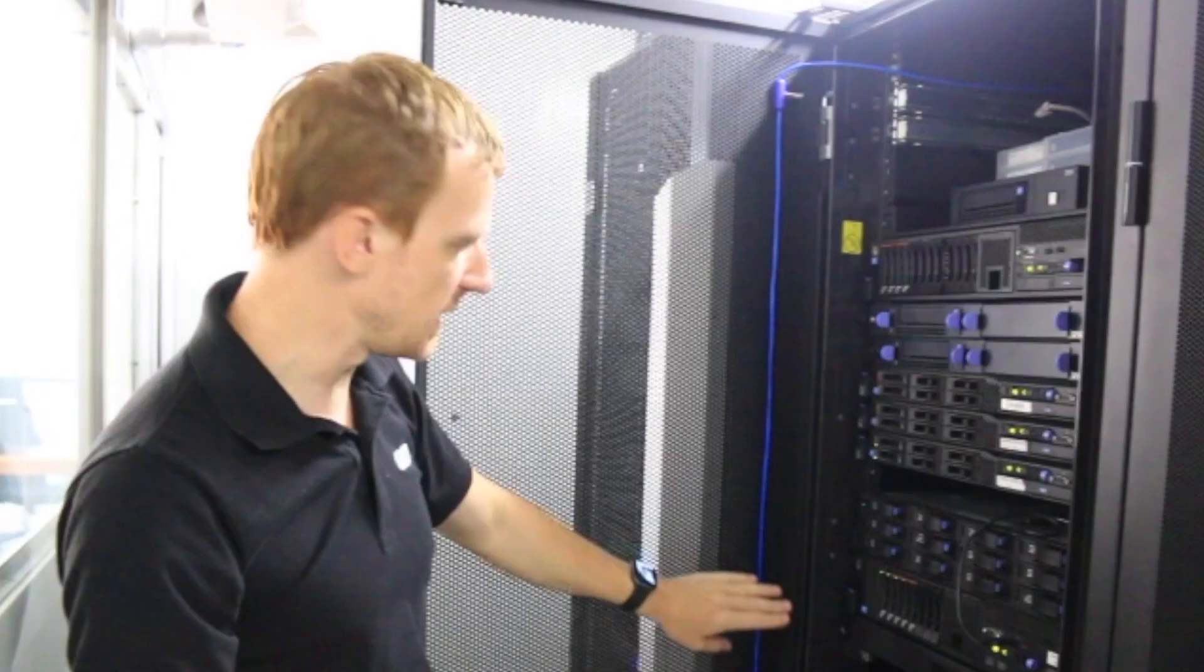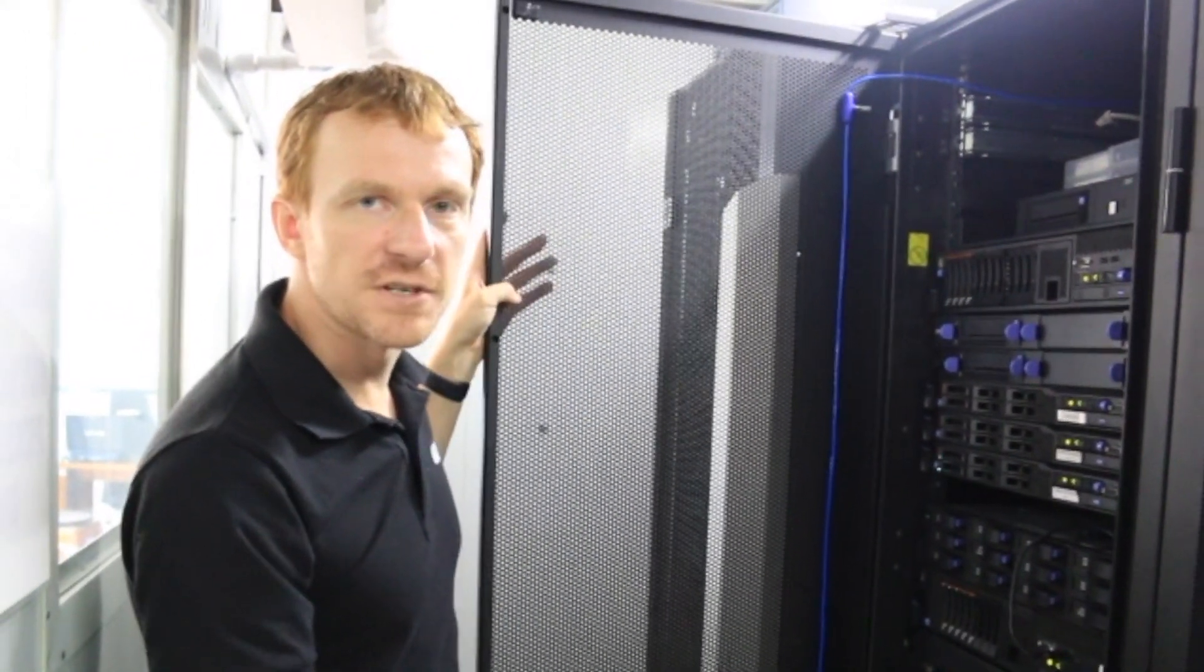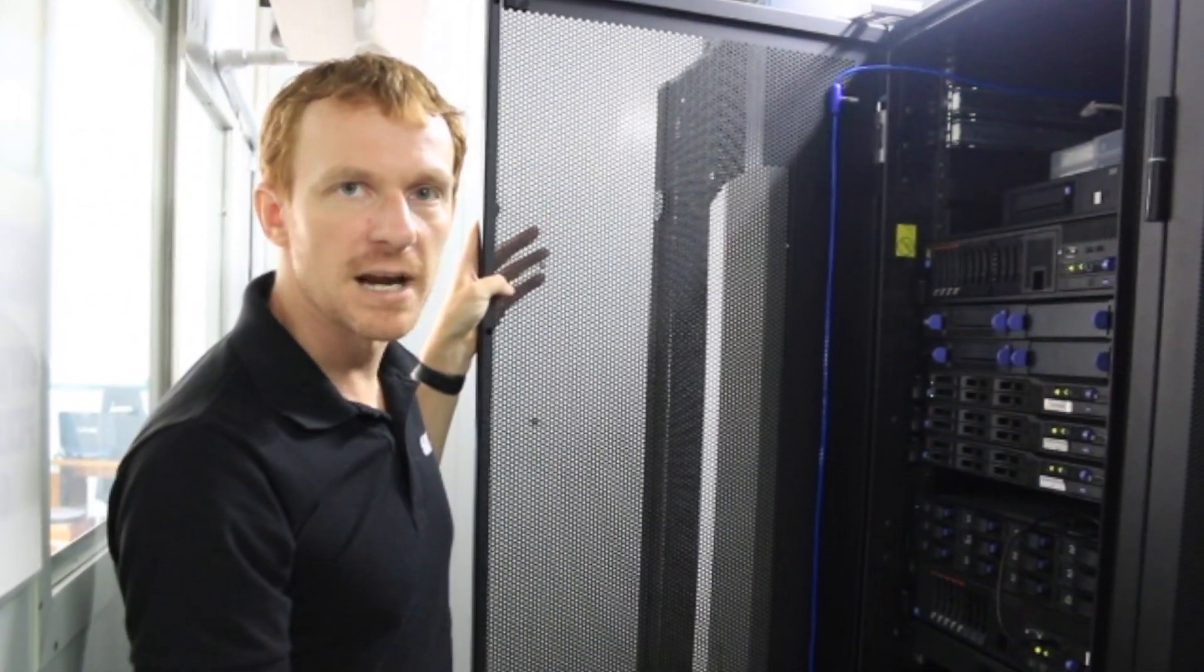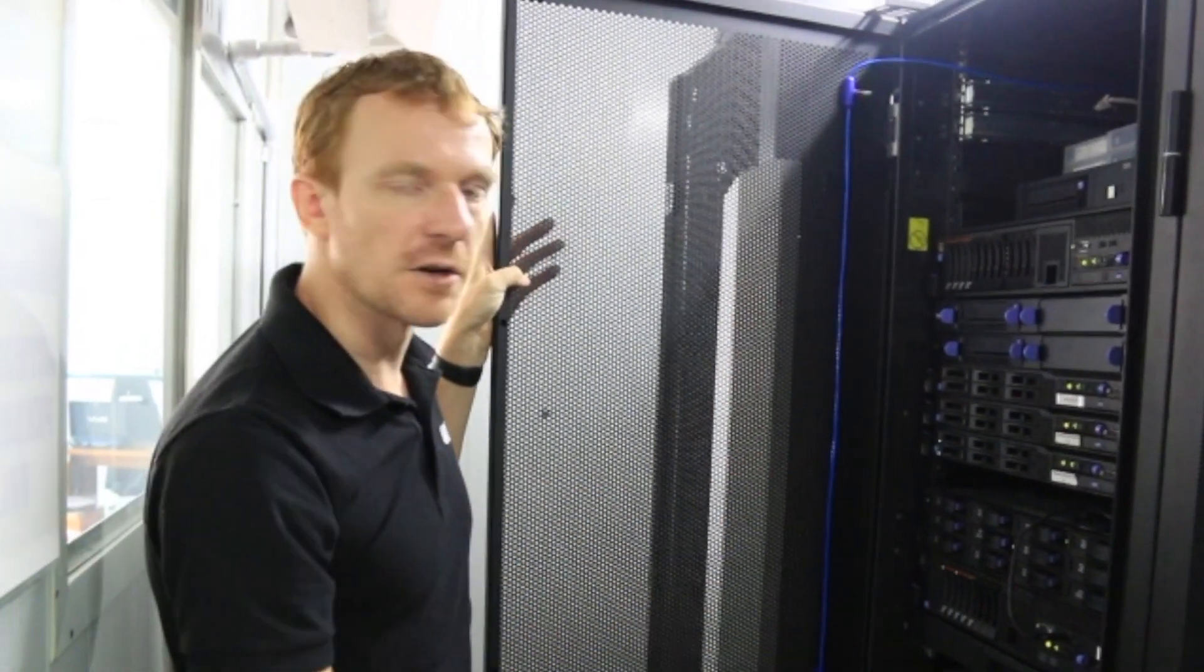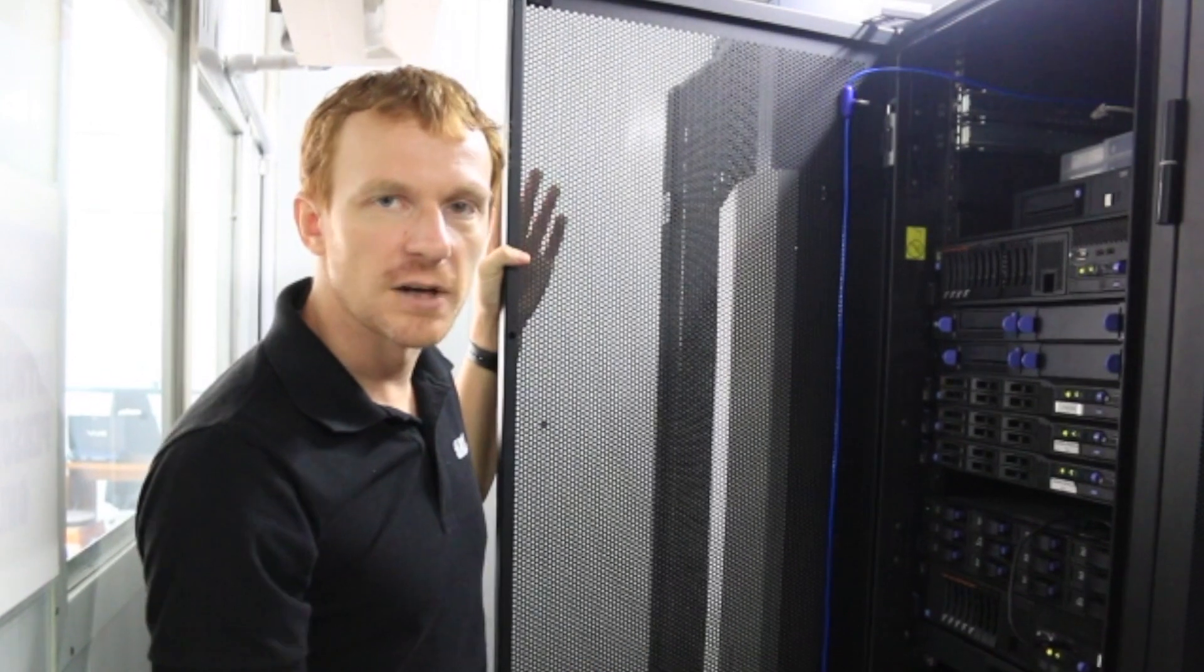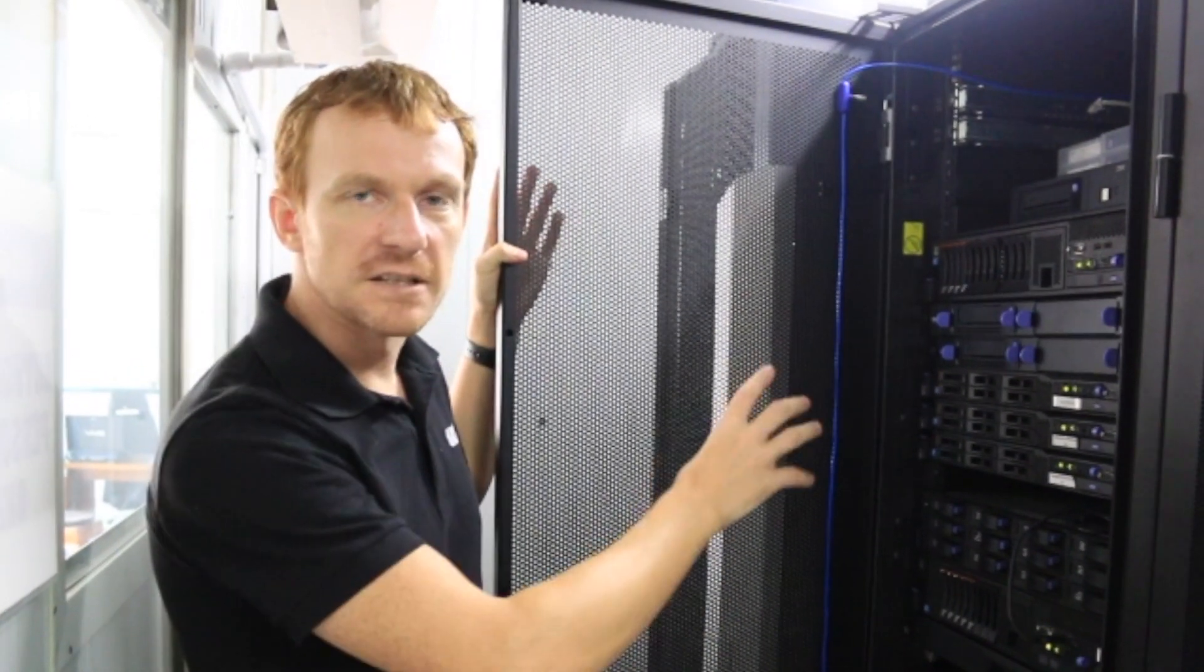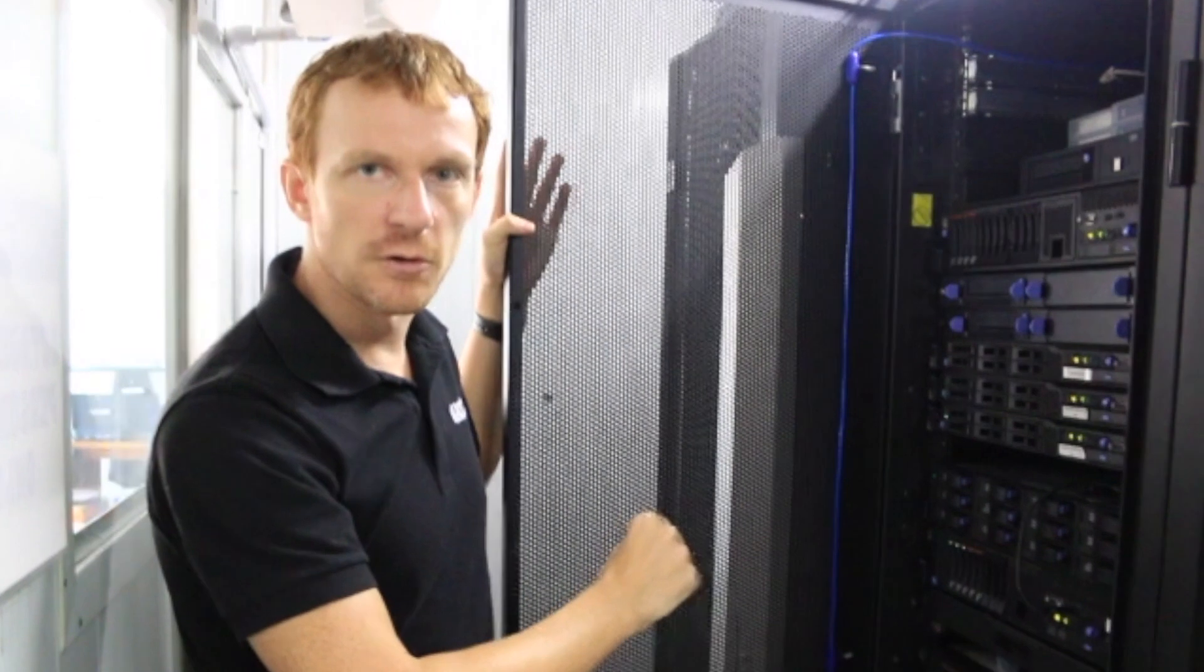and back, humidity front and back, as well as the Delta T temperature differential from the front to the back of the rack. This way we can make sure that all of the servers and equipment in here are running at the right temperature and we haven't got any hot spots.